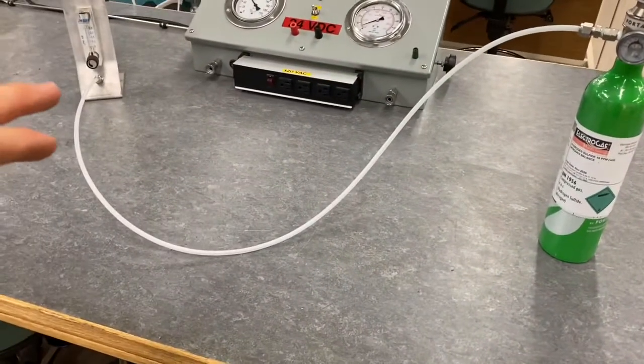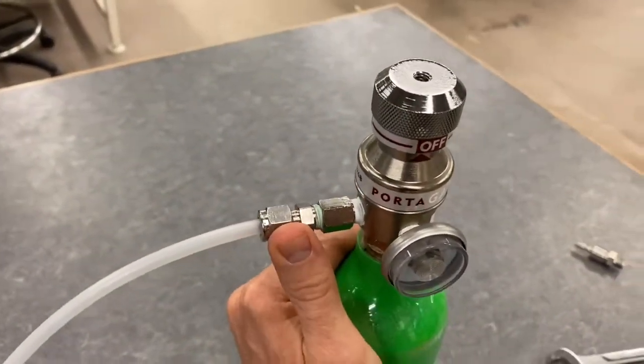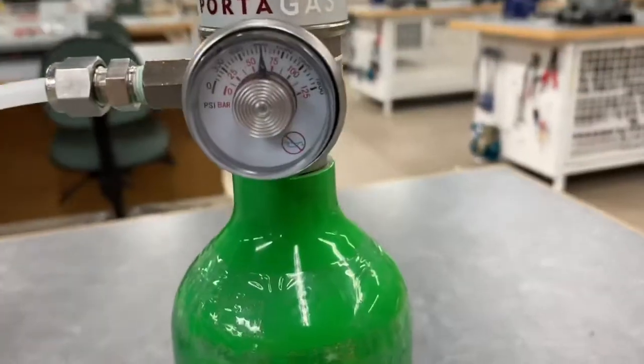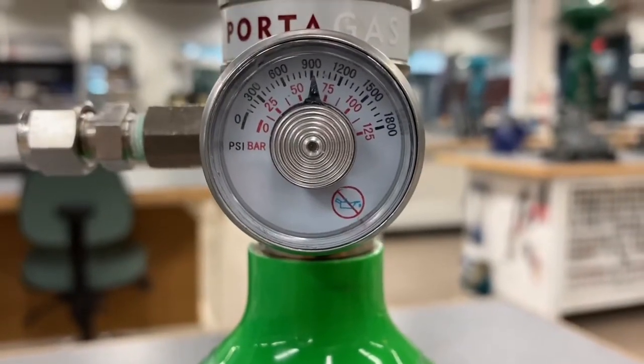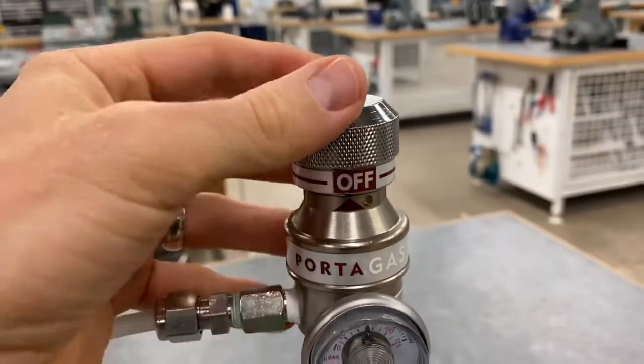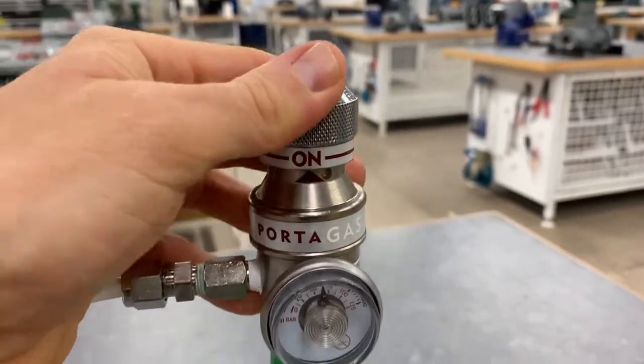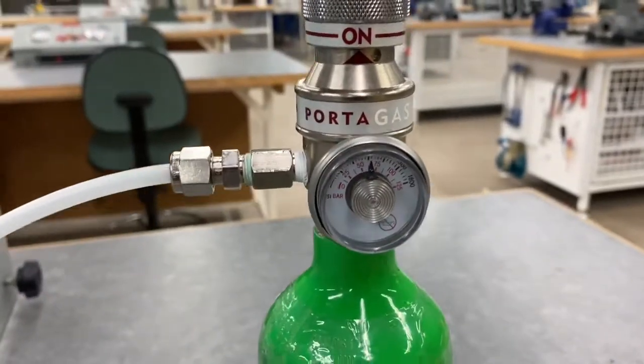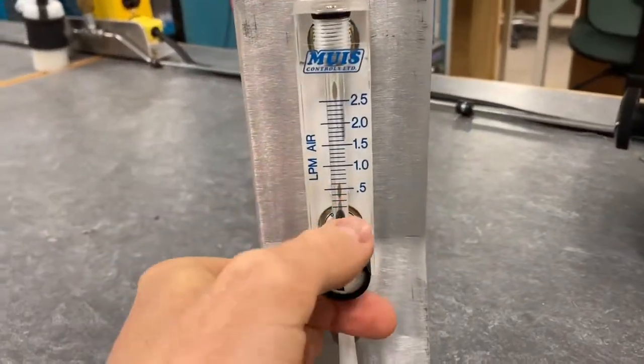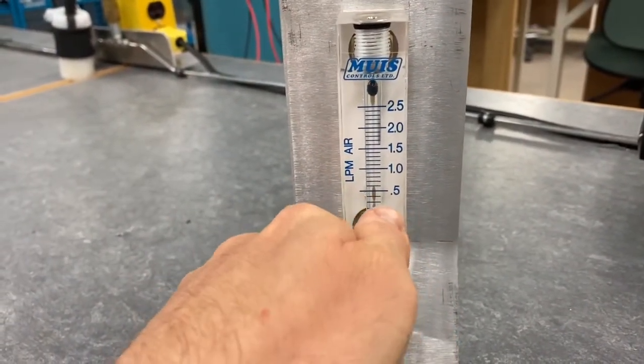Now you can see I've removed the tubing and connected it to the regulator. I've threaded this onto the top of the calibration gas. It just needs to be hand tight. If we have a look here on the gauge, you can see it's reading 900 PSI in black. All I have to do is push down and twist and it will start flowing gas. Once I have it to on, we should now be flowing gas and it'll be flowing out to our variable area meter. I have this shut right now, but once I open it, you can see we have gas flow.